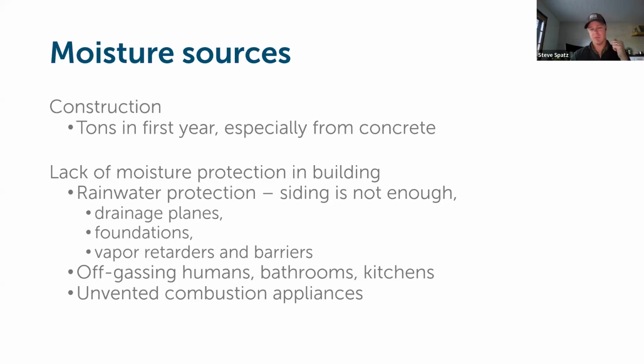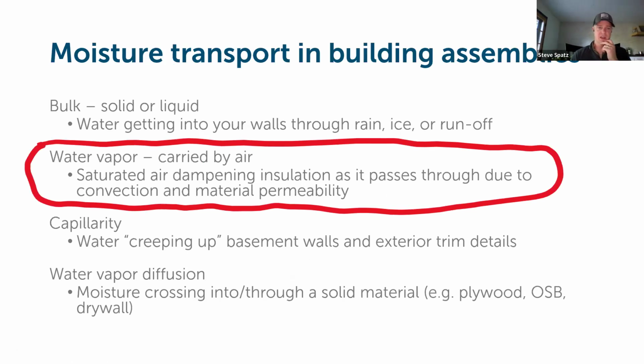We are building very tight building envelopes at this point, because the less air movement you have through building assemblies, the less transport of moisture vapor you get in the first place. But that also means that there's not a passive way for air exchange to occur anymore. The old buildings that were not built with any intention to try to have good air tightness and even thermal insulation have a lot of air moving through them. And so, those assemblies in these older buildings can load with a lot of moisture, but there's so much air movement through the building that moisture eventually leaves those components and dries out. We no longer have that happening with modern construction. So we really do need a good mechanical system to be keeping things in check.